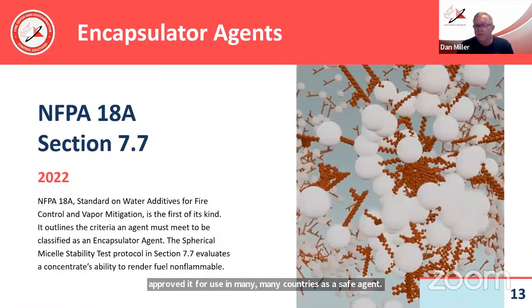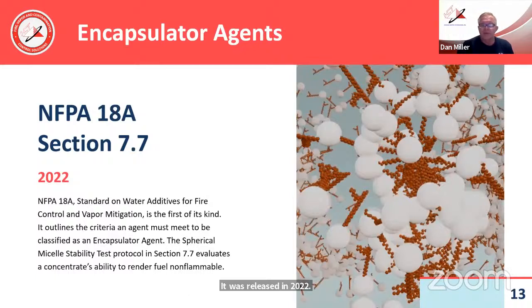NFPA 18A is a relatively new standard, released in 2022, that defines what an encapsulator agent is, whereas NFPA 11 covers foams and the working parameters of foam agents. NFPA 18A defines encapsulator agents specifically, and there's a section, 7.7, which is the testing criteria to determine whether an agent truly is an encapsulator agent.